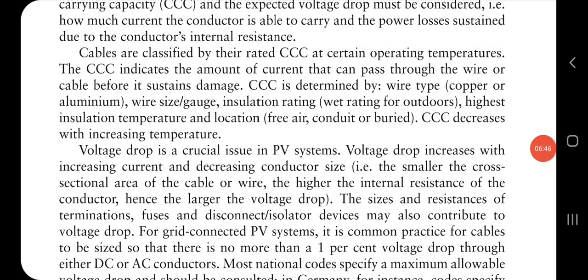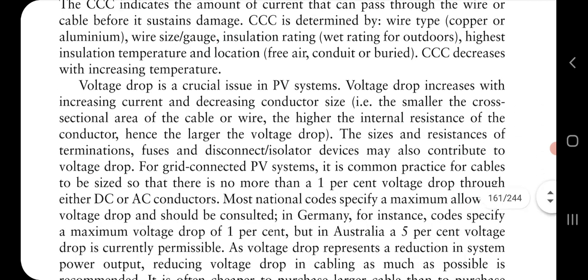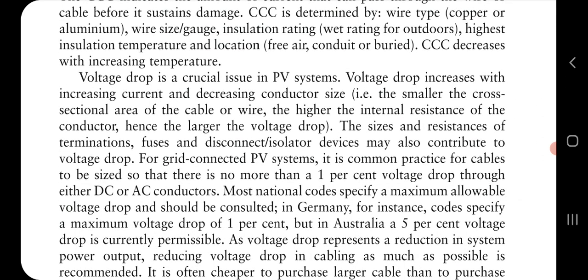Now, when we are determining the cable, we have to determine whether it is aluminum or copper. The size or gauge, insulation, and location are also considered, and these play a very important role. Voltage drop also plays a very important role. When the current increases, voltage drop also takes place. And if the size of the conductor decreases, the voltage drop increases a lot.